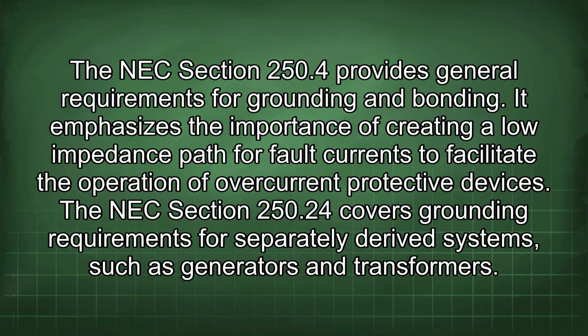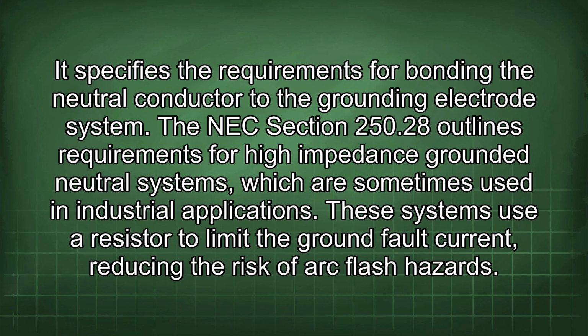The NEC Section 250.4 provides general requirements for grounding and bonding. It emphasizes the importance of creating a low impedance path for fault currents to facilitate the operation of overcurrent protective devices. The NEC Section 250.24 covers grounding requirements for separately derived systems, such as generators and transformers. It specifies the requirements for bonding the neutral conductor to the grounding electrode system. The NEC Section 250.28 outlines requirements for high-impedance grounded neutral systems, which are sometimes used in industrial applications. These systems use a resistor to limit the ground fault current, reducing the risk of arc flash hazards.